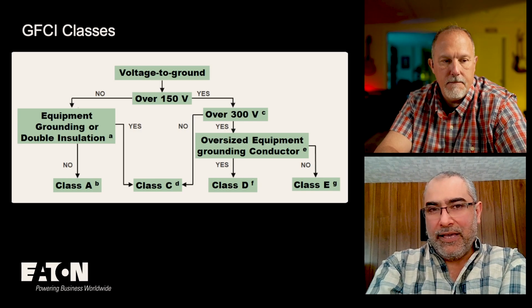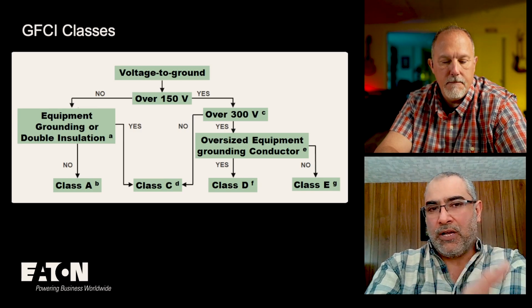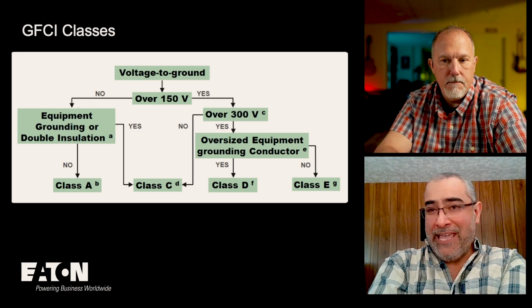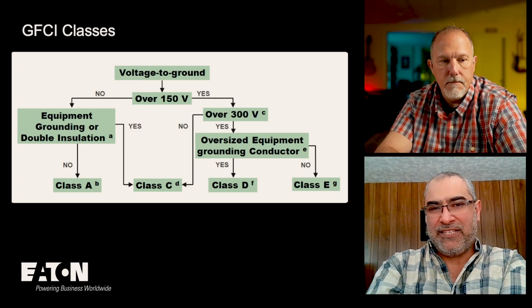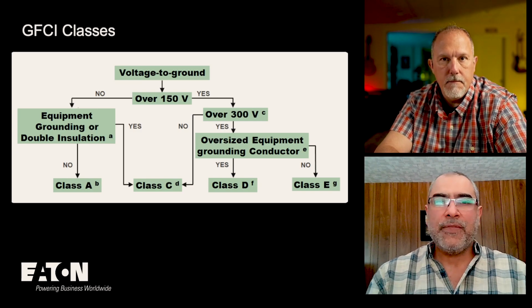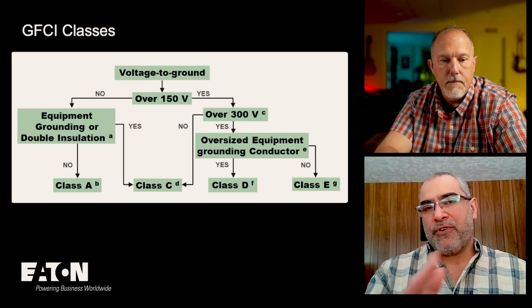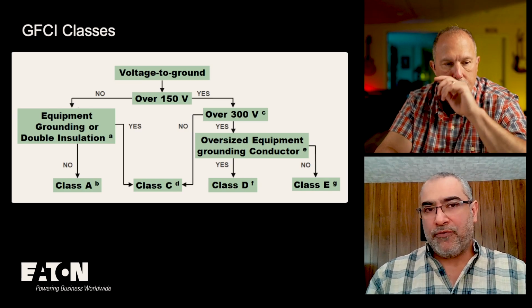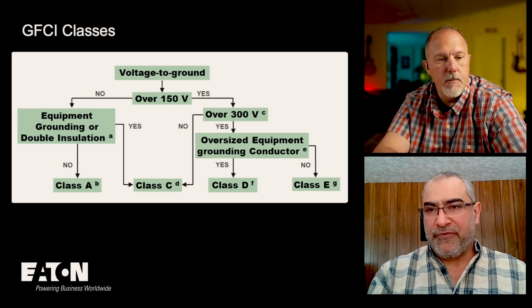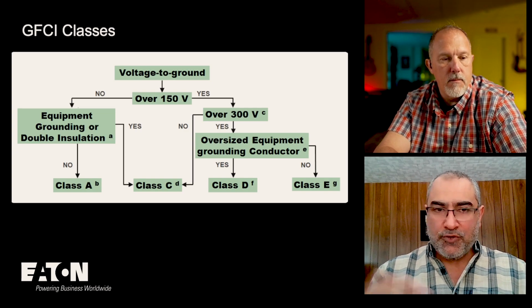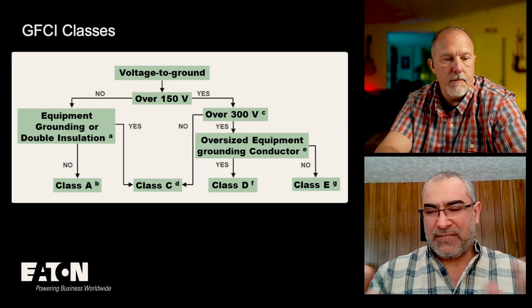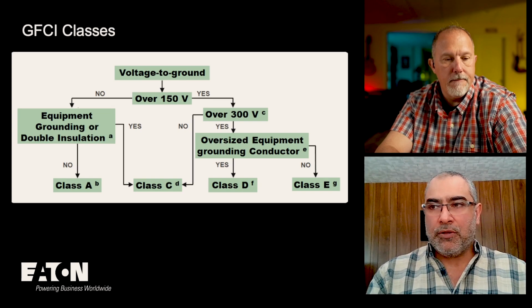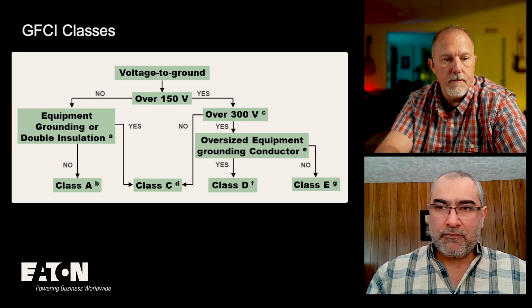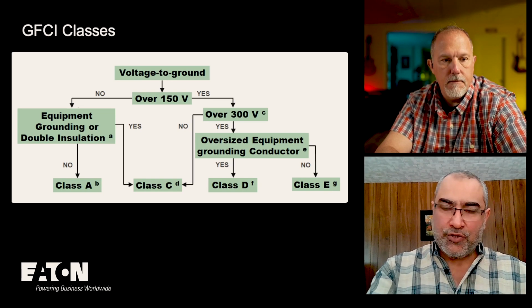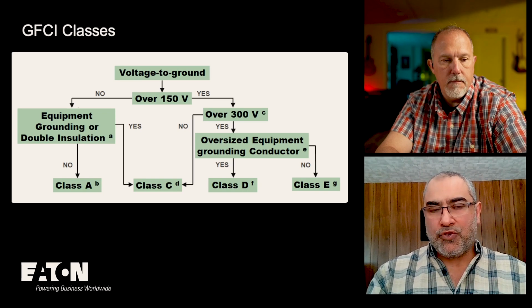So this is 943B. And when UL proposed this idea of new classes of GFCIs, they had UL 943A and B, so this became C. But it has nothing to do with Class C, because I know people may think it's a Class C thing. No, it's not. The demarcation between the different classes is the voltage to ground of your circuit. If your voltage to ground is less than 150 volts, which is typically what we would see at homes, that's the Class A GFCI, the 4 to 6 milliamp one that we're so used to. It is mainly installed in residential applications and maybe light commercial, on 240 volt or less circuits, like 120 volt circuits, where the voltage to ground is always less than 150 volts.